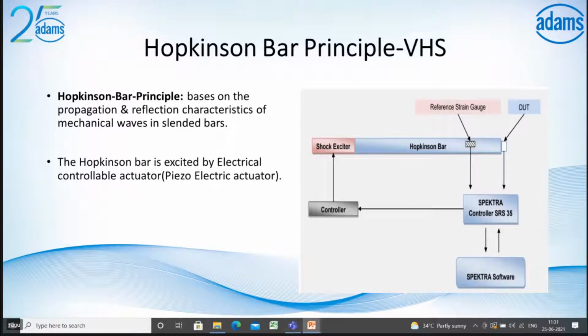So how is it working? To test and calibrate acceleration sensors, within a barrel, a projectile is accelerated pneumatically, hitting the end of the bar from an adjustable distance, exciting the strain pulse within the bar. The pneumatic control allows the projectile to be retracted after each shot by applying a negative pressure, and to generate a shock. So you can see the DUT is mounted over here, and this will be excited, which gives the movement, the reflection of the Hopkinson bar, which excites the strain gauges, and it will measure the shocks, and the DUT will be getting calibrated.